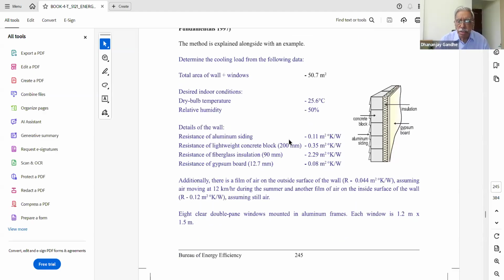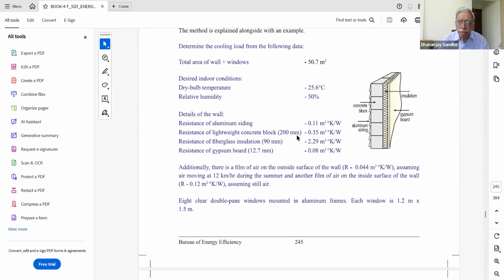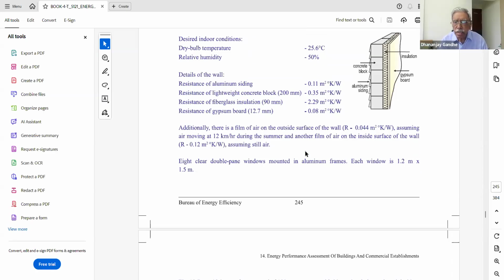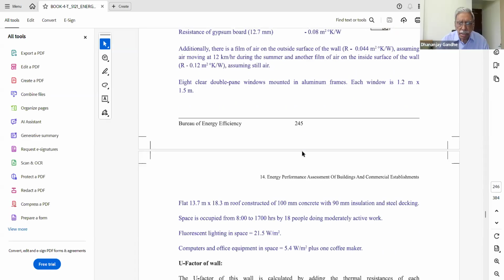Second, the desired inside conditions are required at 25.6 degrees. Relative humidity to be maintained is 50 percent, and the details of the wall, the values are given here, especially the walls having aluminum windows. So the R values for aluminum siding and concrete block and insulation and so on are given here. Okay. In addition, it's mentioned that there is a film of air outside the wall and also above the roof, which also contribute to the air conditioning load. The air is moving at a rate of 12 kilometers per hour.